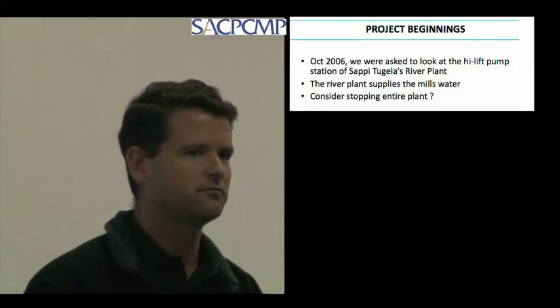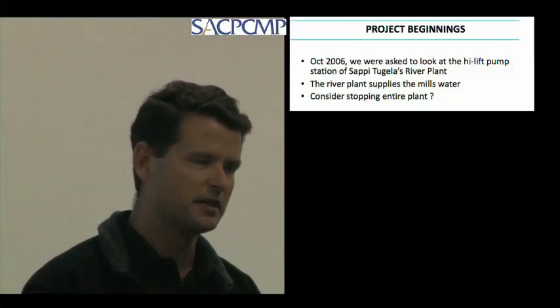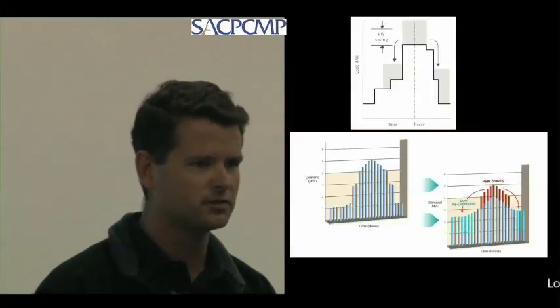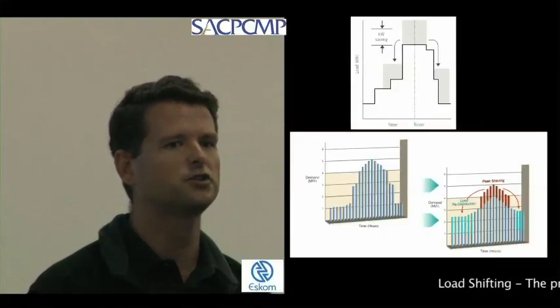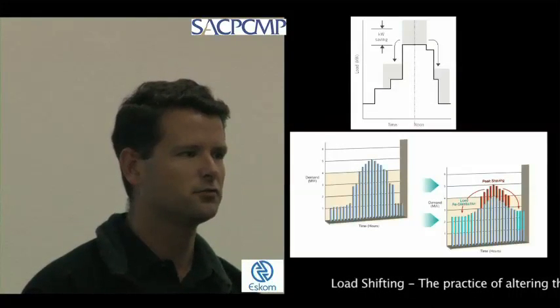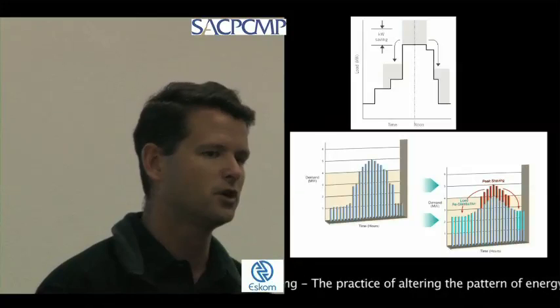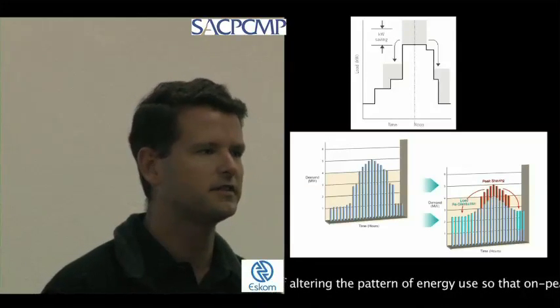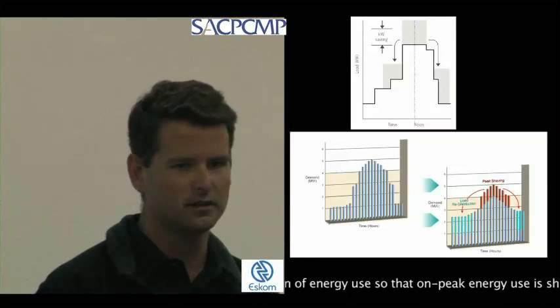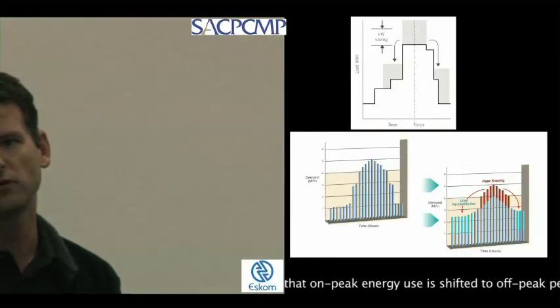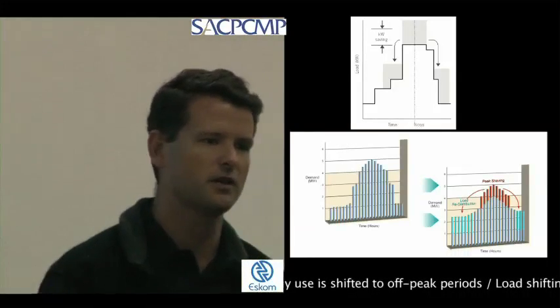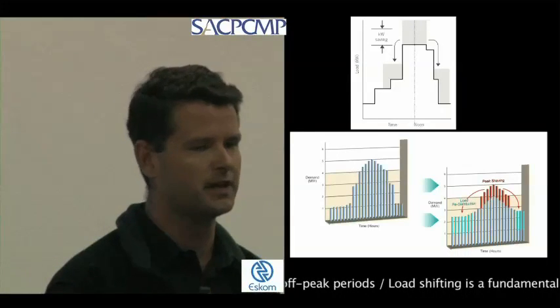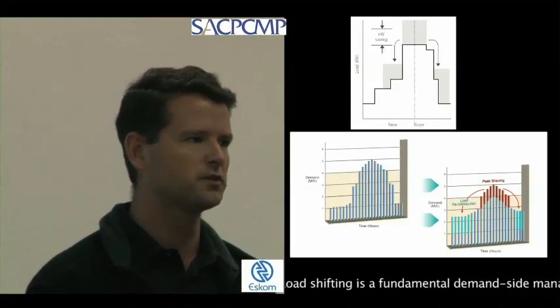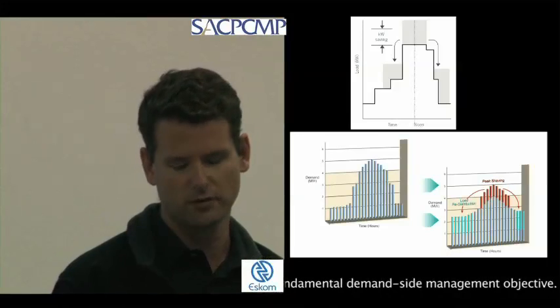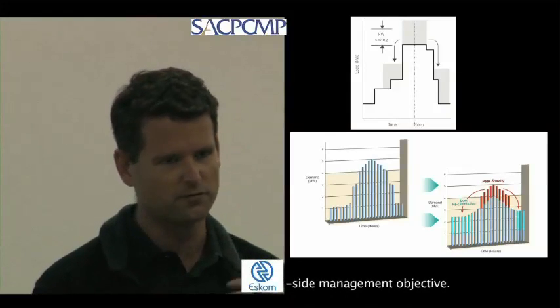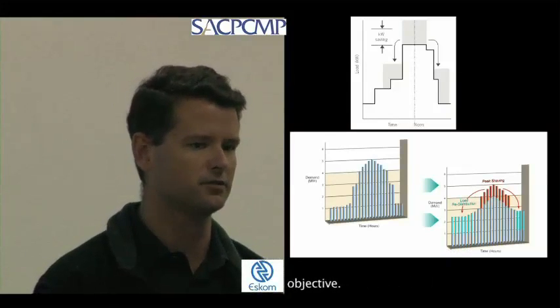Just to go back a bit, with Eskom we had all this load shedding floating around, and Eskom was funding load shifting projects. For those of you who don't know, load shifting is when you switch off a plant during peak periods of the day so that you can counteract the peak on the grid. That's because of everyone going home and switching on their stoves and geysers, and Eskom has this peak that they struggle to handle. So the idea is to switch off plants during that period of the day and counteract that peak. And Eskom was funding those types of projects quite heavily and pushing for them.